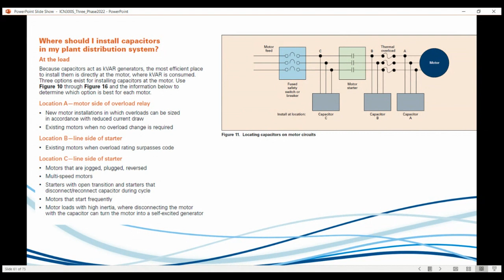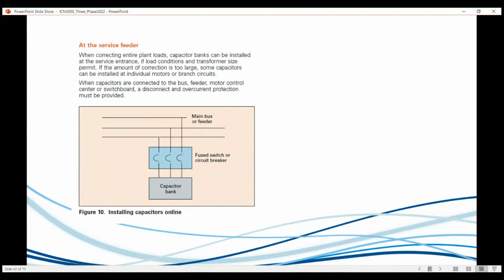So what they are essentially explaining there is 3 different cases where you ideally want to connect it at the motor side of the overload relay, or the line side of the starter, or also location C. So you typically want to connect it as close to the motor as possible. If you have the service feeder, or where the main bus is, you typically want to connect the capacitor bank there. As they say, capacitor banks are installed at the service entrance if load, condition, and transformer size permit. If the amount of correction is too large, some capacitors can be installed at individual motors. So it's a two-way approach in terms of where you want to connect the capacitors.